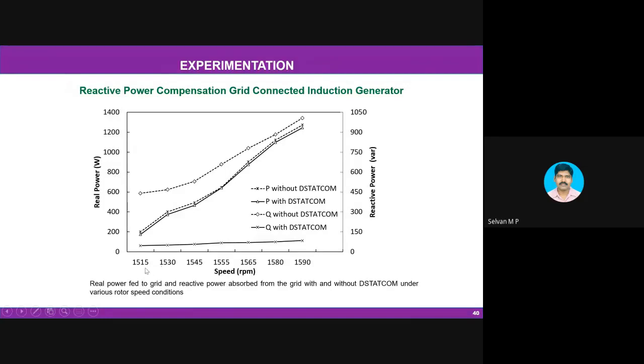So you can see that if you vary the speed, there is an increase in real power. As speed increases, real power also will increase. That is the property of induction machine based wind farms. As real power increases, reactive power is also increasing. So this is the Q demand without STATCOM: Q demanded from the machine, Q demanded from the grid. Right. So if you want to generate 1 per unit, you need to supply nearly 1 kVAR. That depends on the machine. As a thumb rule, 1 per unit real power output from the machine requires nearly 0.5 to 0.6 per unit of reactive power.